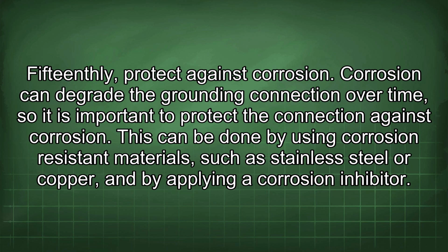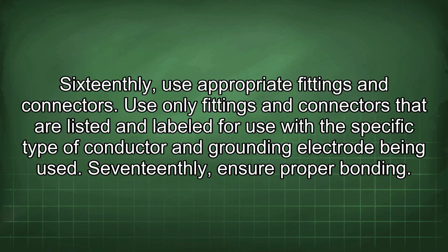Corrosion can degrade the grounding connection over time, so it is important to protect the connection against corrosion. This can be done by using corrosion-resistant materials such as stainless steel or copper, and by applying a corrosion inhibitor. 16thly, use appropriate fittings and connectors. Use only fittings and connectors that are listed and labeled for use with a specific type of conductor and grounding electrode being used. 17thly, ensure proper bonding.